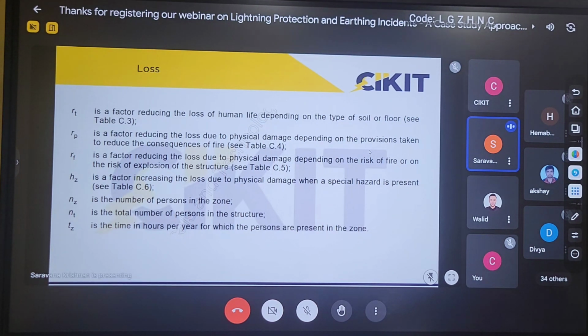And HZ is the special hazard, which is very specific to the particular conditions. nz is the number of persons in the zone. In this risk assessment, we are mainly concentrating on the protection of human beings. So if the number of persons on the particular site is higher, the risk will also be higher. If the number of persons is much lower, for example in a solar power plant, the area will be much larger, whereas the number of persons will be very low. Only 5 or 10% will be operating the entire plant. So the area will be higher, but the number of persons will be lower. If I take hospitals, the area will be lower, but the number of persons will be higher. Also, schools or colleges: the area might be lower, but the number of persons will be much higher. So when considering damage or injury to human beings, if the number of persons is higher, the risk and the losses will also be higher.